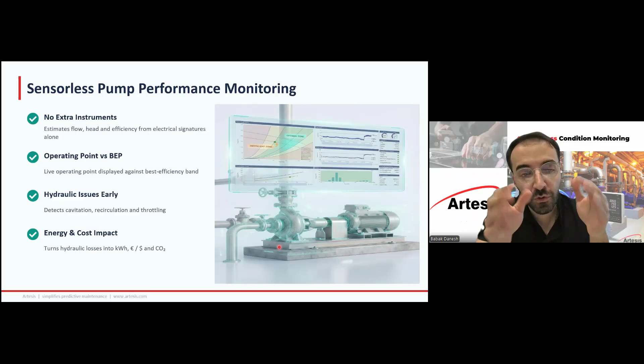Let's talk a little bit about one of the much more attractive features, which is pump performance monitoring. No extra instrument needed. You can easily observe. We have one great case study that I will show you. We got the prize from the Turkish Ministry for this case study. We can provide you the data for best efficiency point and your current operating point, so you can see yourself where you are - in the green zone, which you should be, or in the region that is inefficient.